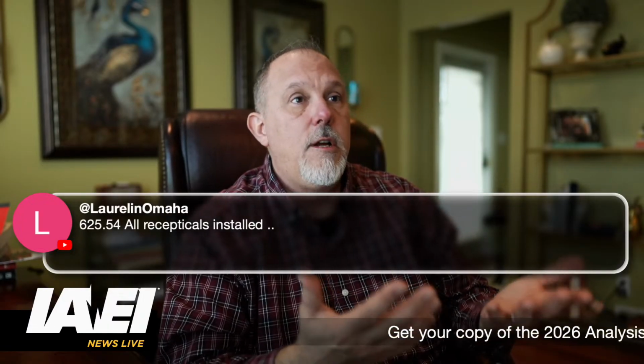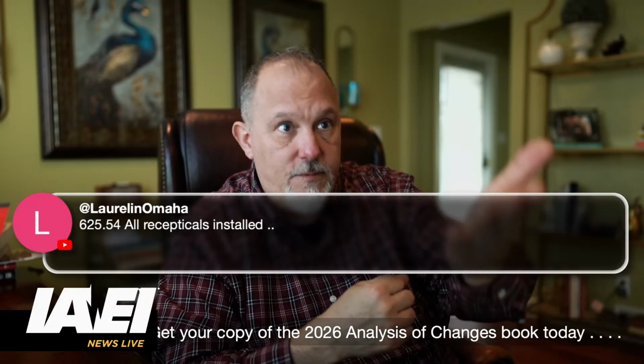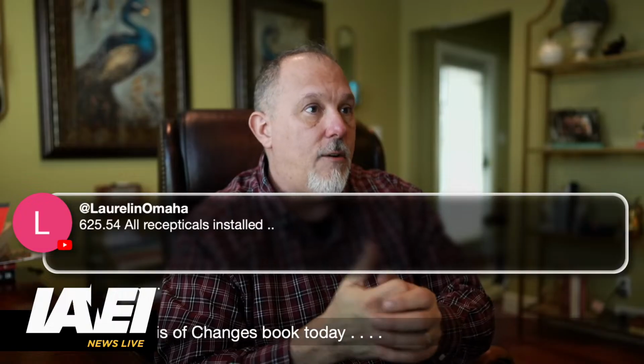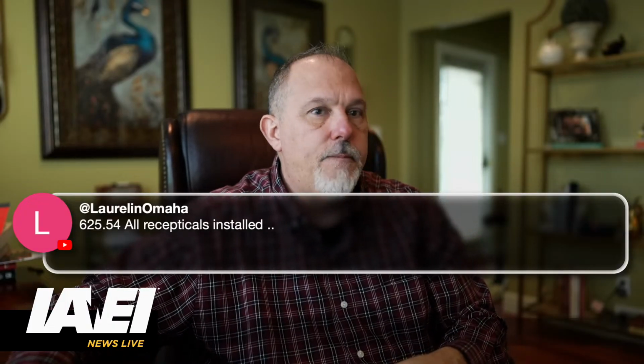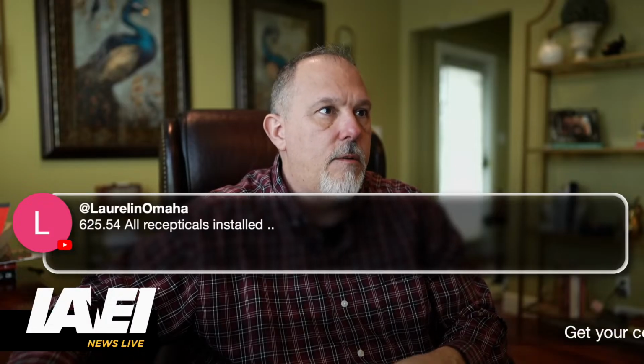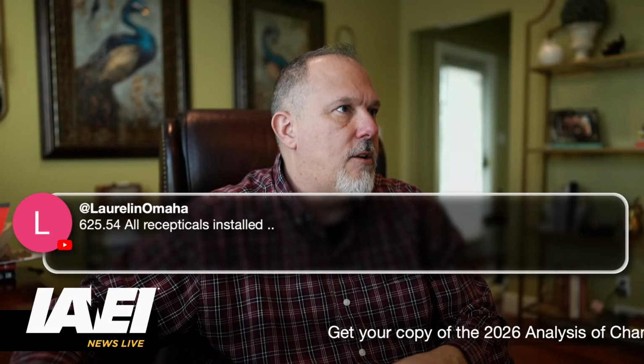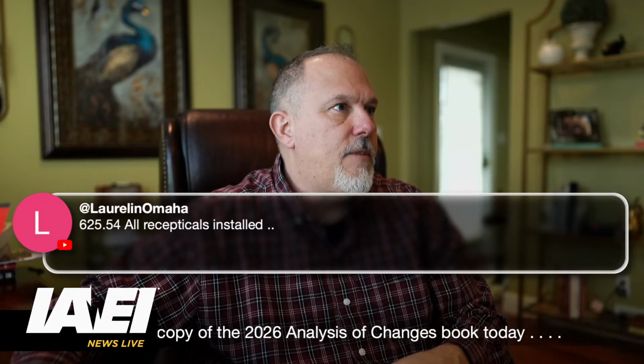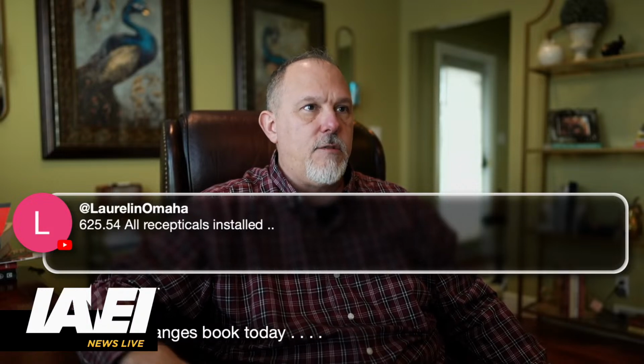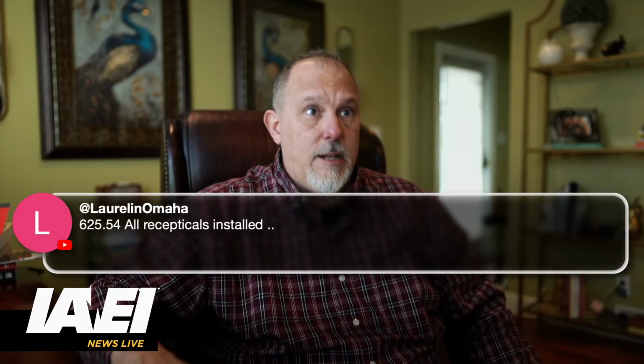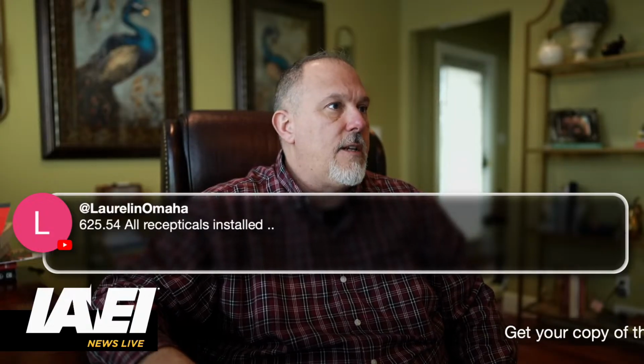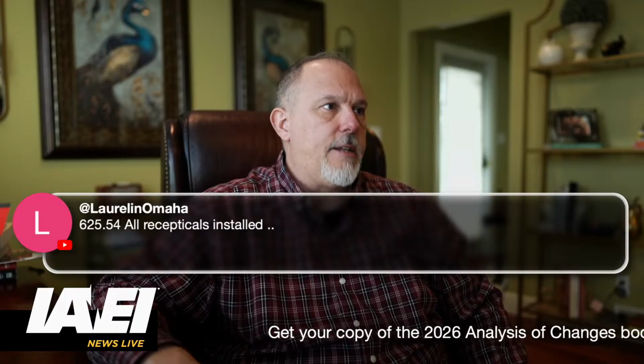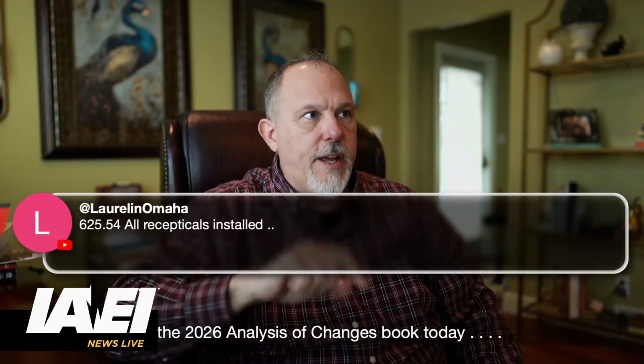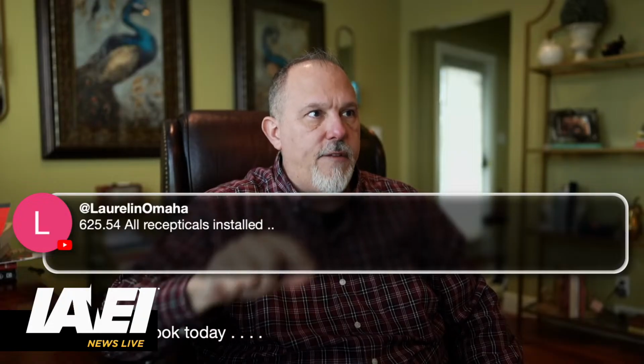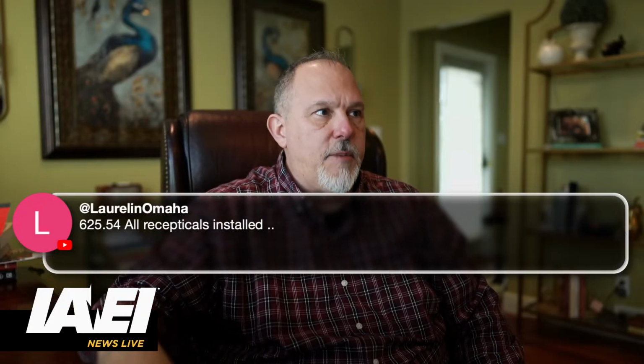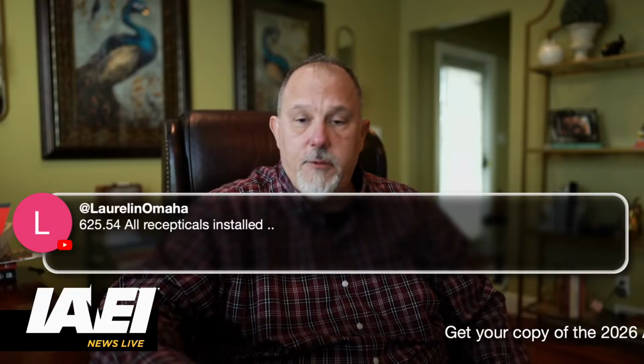So if I have an outdoor vehicle charger at 60 amps, single phase, or less to ground - let me come back to 210.8F. It says for dwellings, all outdoor outlets other than those covered in 210.8A, including outdoor outlets installed at the following locations, single phase branch circuits, blah blah blah, shall be GFCI protected. So I still have this requirement: single phase branch circuits rated 150 volts or less to ground, 60 amps or less, have to be GFCI protected. There's nothing in here for three phase.